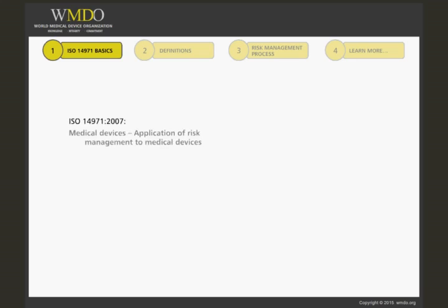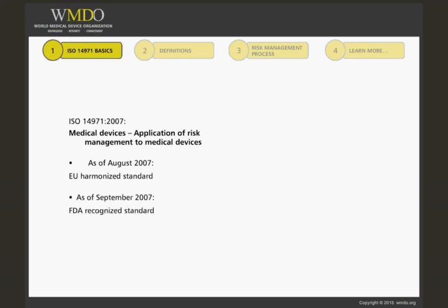Here's some more basic information about the ISO 14971 standard. It's good to know that it is accepted by the European Union as well as the FDA. In Europe, the EN ISO 14971-2007 is accepted as a harmonized standard — an accepted way to meet the risk management requirements as contained by the medical device directives, which include the MDD, AIMD, and IVD. It also is an FDA-recognized standard, making it doubly worthwhile to follow if you are dealing with both European and US medical device regulations.